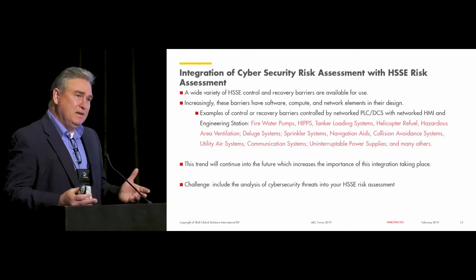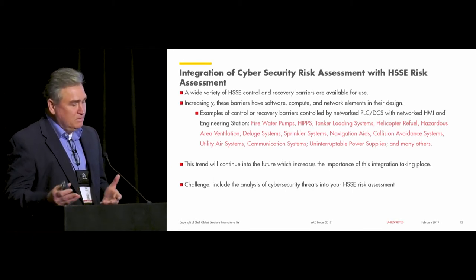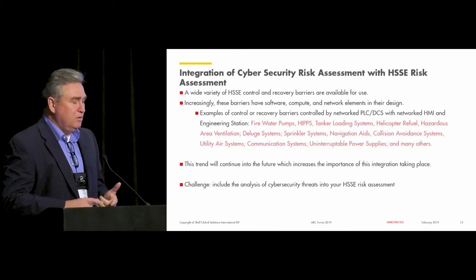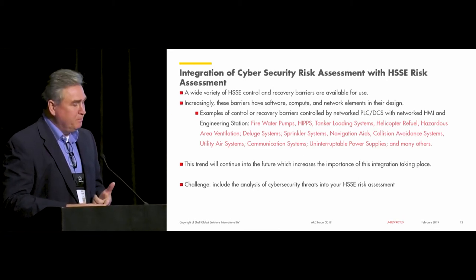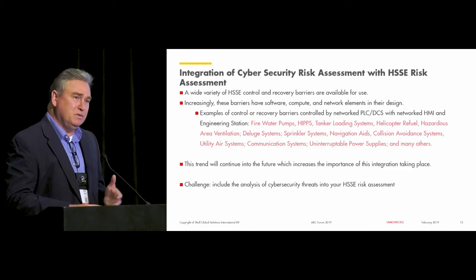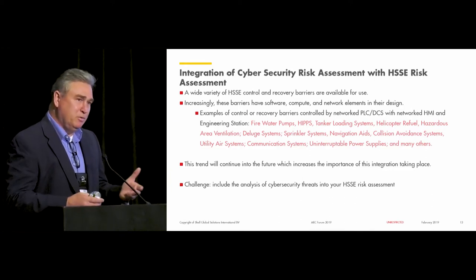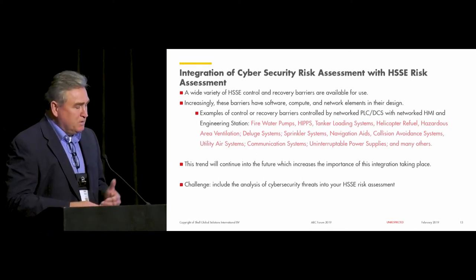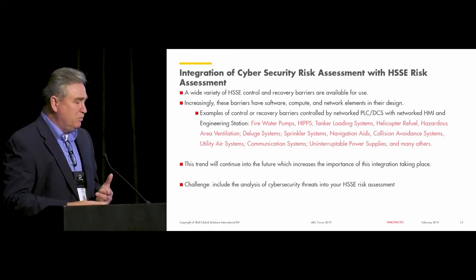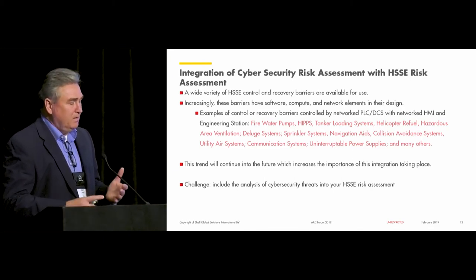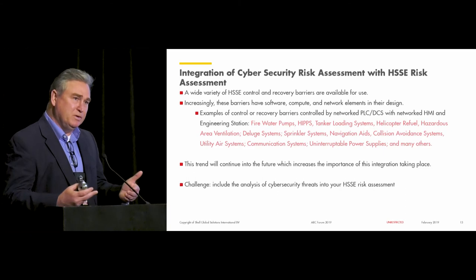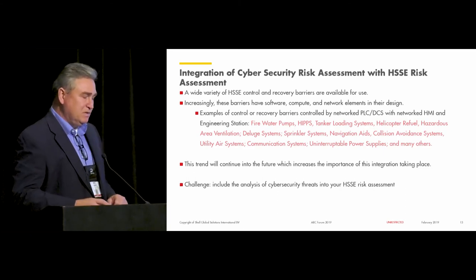We talk about SIS and cyber vulnerabilities a lot, but there are many other types of safety barriers. Firewater pumps are an example of a recovery barrier. Navigation aids and collision avoidance systems are taken credit for and associated with risk reduction related to top events like a collision. So it's not just SIS — we have to expand our thinking beyond that. This trend will continue into the future as more of the safety barriers we can pick from have cyber vulnerabilities.